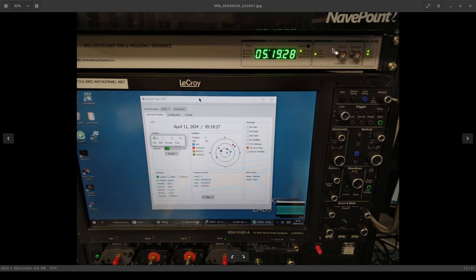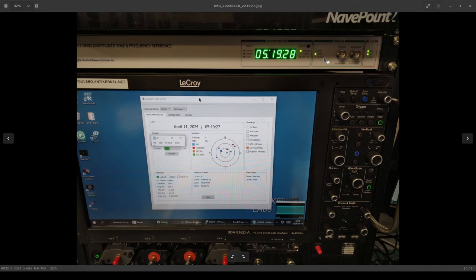Anyway moving on to the right we can see there's a couple more status indicators. The lock indicates that it does have a PLL lock. The stable light is off here again. This picture was taken right after the unit was powered on and so it was still syncing the local oscillator to GPS and hadn't yet gotten quite where it wanted to be. And then the holdover LED will turn on if it loses GPS sync and is running off the local oscillator only.